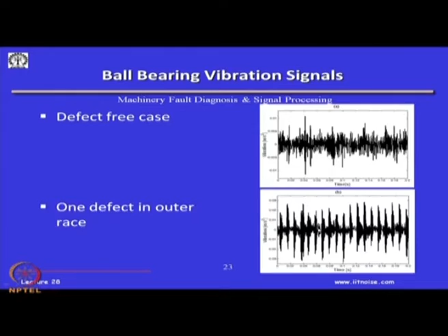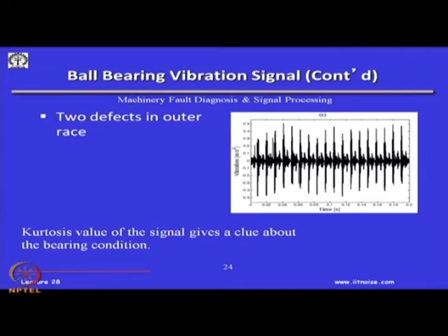And this kurtosis value gives you an indication whether a fault has occurred in the bearing itself. You blindly pass it through a signal processor wherein you just calculate the kurtosis of the time domain signal. Kurtosis gives the peakiness of the signal. And usually a kurtosis value greater than 5 is a defective case, and less than 3 is the normal case.